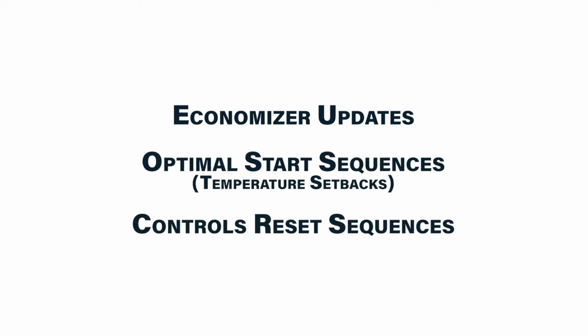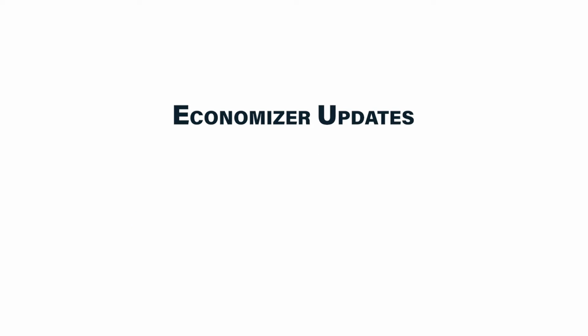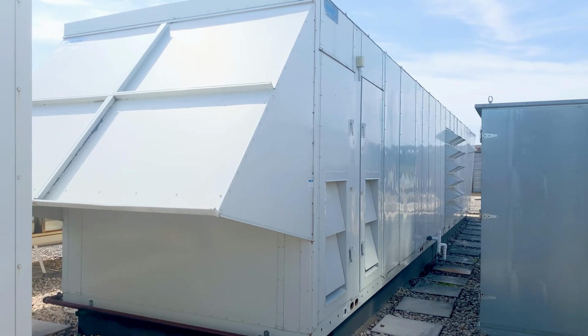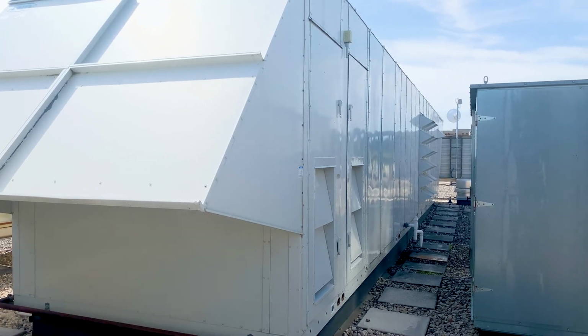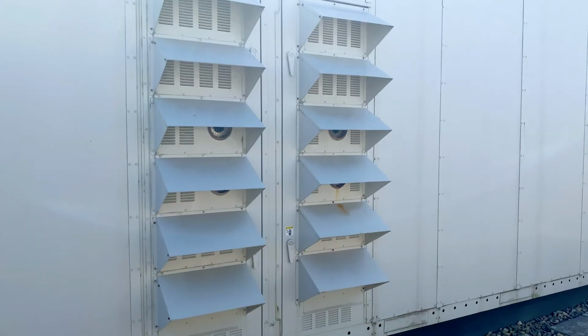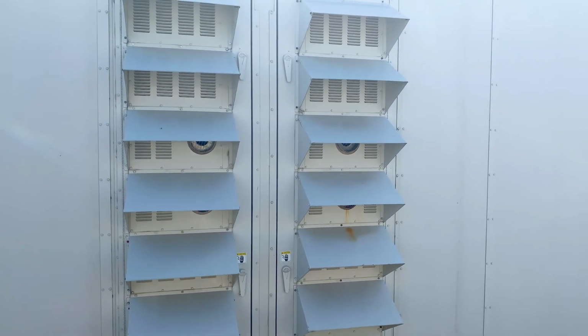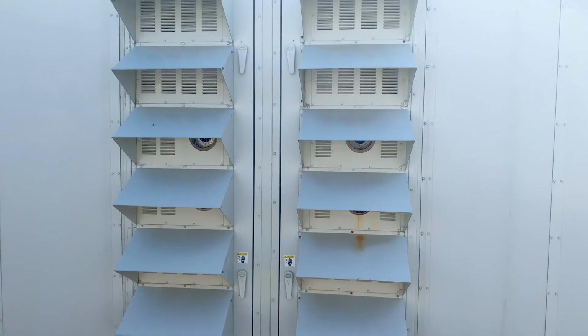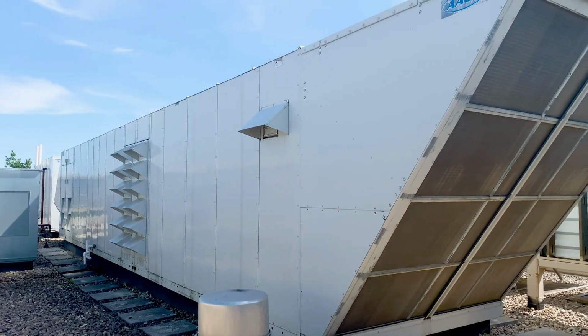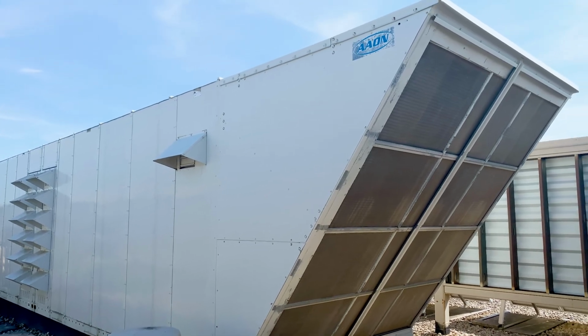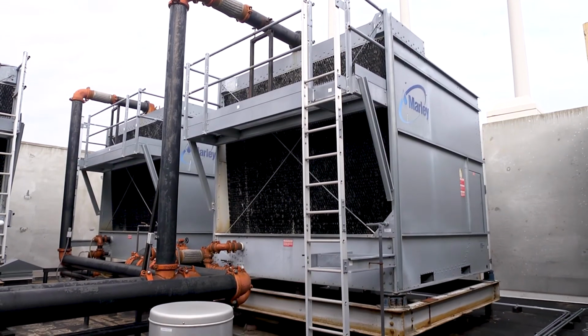The first HVAC controls update I want to discuss are updates to the economizer requirements. Many of you already know what an economizer is, but for those of you who might not be familiar with them, economizer mode is simply using outside air to condition the building when it's more economical. There are 2 types of economizers: air side economizers and water side economizers.